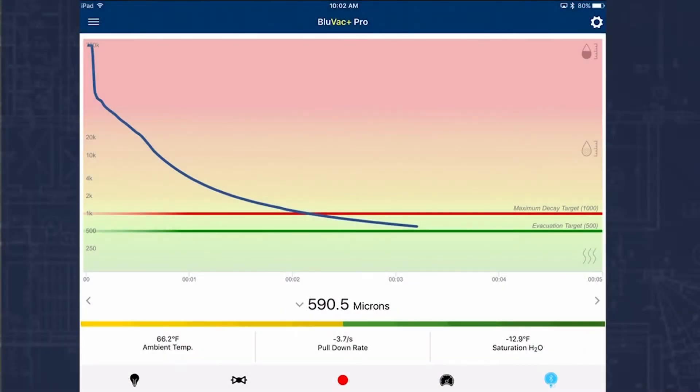We're down to about 591 microns. If I tap on the side here you can see our total elapsed time — we're at 3 minutes and 19 seconds. You can see our time below target test which right now is at one minute. When the reading crosses the threshold of 500 it's going to start to count down, because we want to hold this below 500 microns for one minute in this test. We can see our ambient temperature of 66.2°, our pull-down rate of about 3.7 microns per second, and the saturation temperature of water at about negative 13. We're at 495 microns and still coming down.